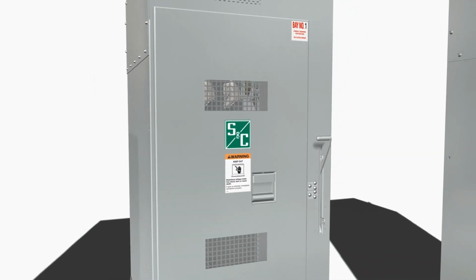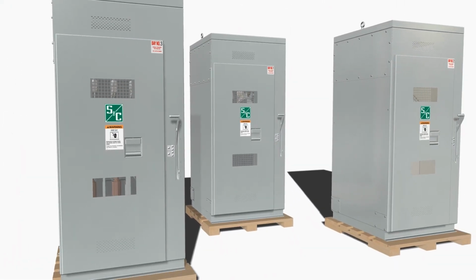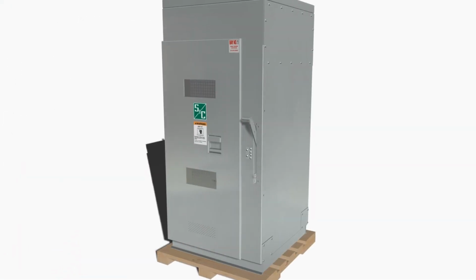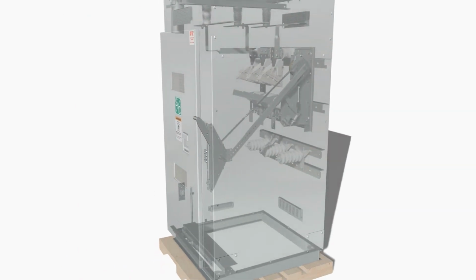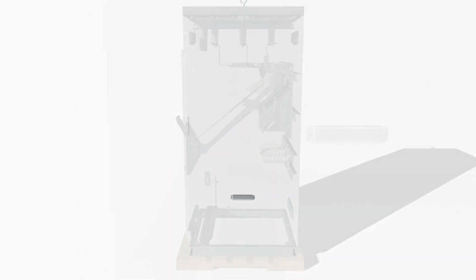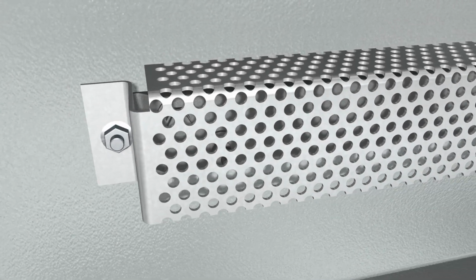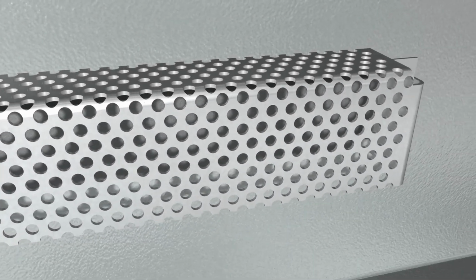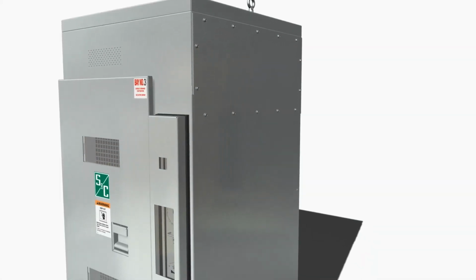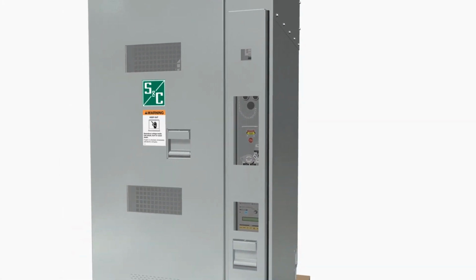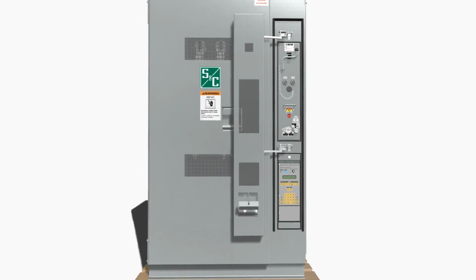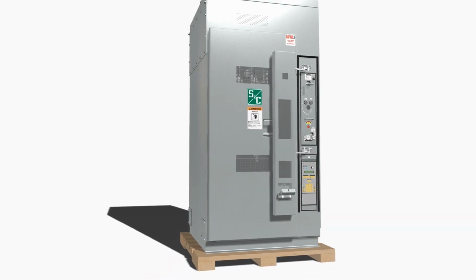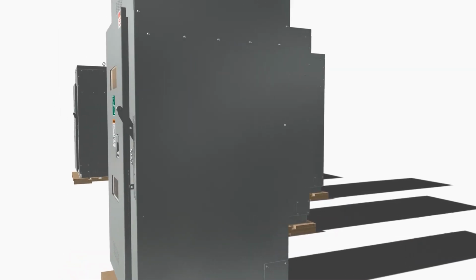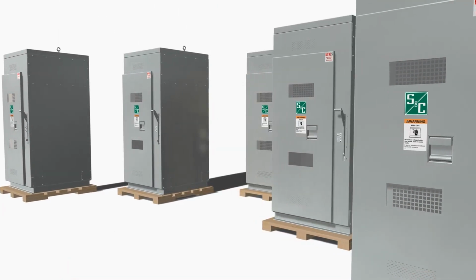The switchgear should preferably be immediately installed in its permanent location. The space heaters, see page 6 of instructions for picture, for outdoor switchgear and indoor switchgear, if so equipped, should be activated at once, even though the switchgear itself may be energized later. This is especially important for bays containing meters and relays, which are particularly susceptible to damage from moisture. See the written instructions for information on storing the switchgear.